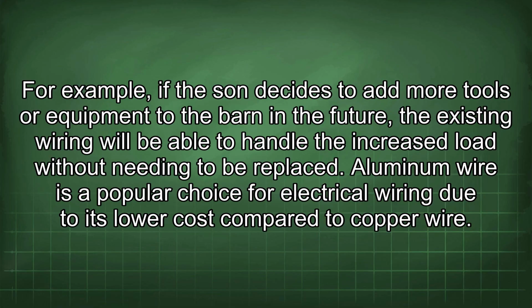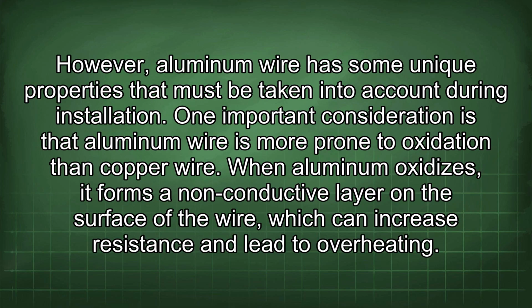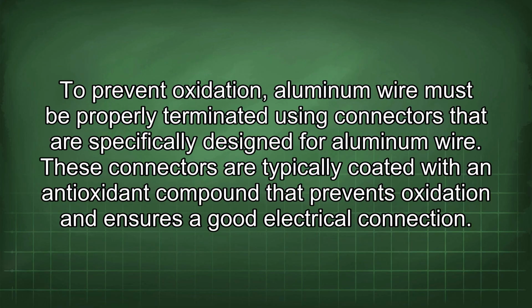Aluminum wire is a popular choice for electrical wiring due to its lower cost compared to copper wire. However, aluminum wire has some unique properties that must be taken into account during installation. One important consideration is that aluminum wire is more prone to oxidation than copper wire. When aluminum oxidizes, it forms a non-conductive layer on the surface of the wire, which can increase resistance and lead to overheating. To prevent oxidation, aluminum wire must be properly terminated using connectors that are specifically designed for aluminum wire. These connectors are typically coated with an antioxidant compound that prevents oxidation and ensures a good electrical connection.